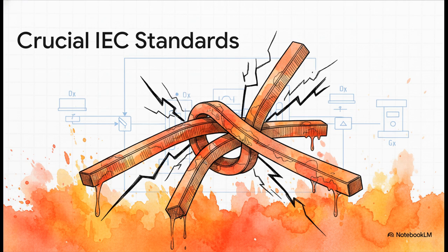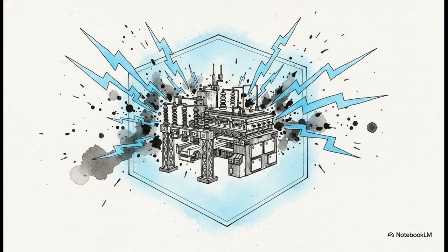It's intense stuff. So the ultimate takeaway here is this. Reliability and withstand are permanently linked. The exact topologies chosen to keep your critical power flowing are the very same ones that demand the most rigorous thermal, mechanical, and electrodynamic verification. The safest layout is very often the hardest one to engineer. You simply cannot design for high availability without also designing for extreme fault survival.